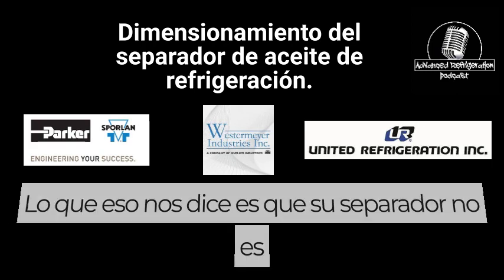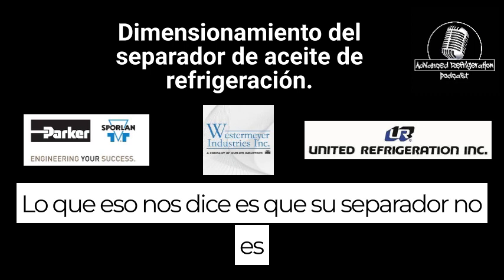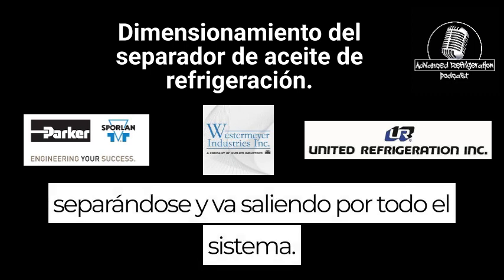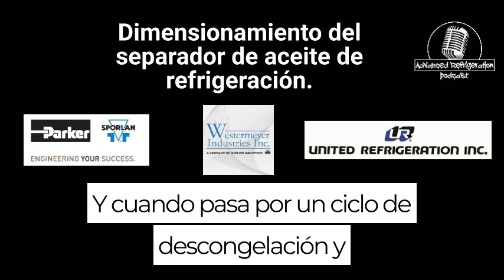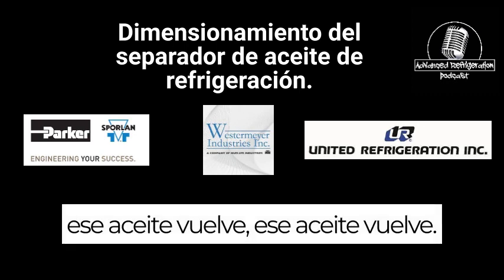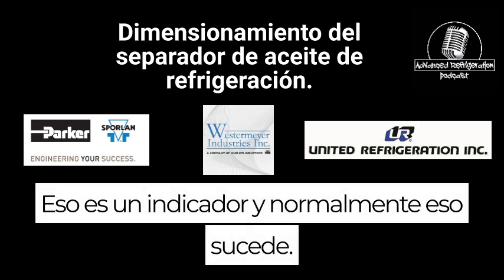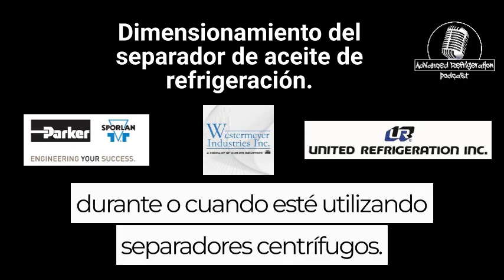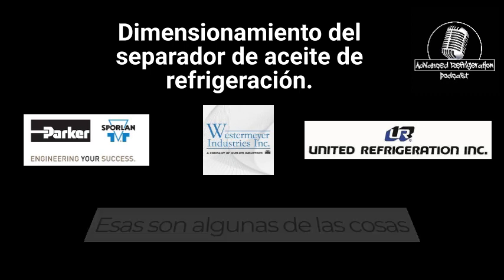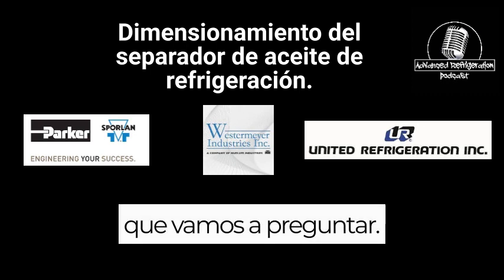What that tells us is your separator's not separating, and it is going out throughout the system. And when you go through a defrost cycle and that oil does come back, that is an indicator. And typically when that happens, you're using centrifugal separators. So those are some of the things that we're going to ask about.